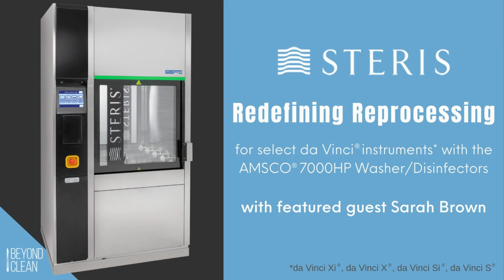something that changed in the U.S. market. Back in 2018, the FDA provided guidance around reprocessing for robotic surgical instruments with the idea that they were trying to help standardize applications there. And what happened was the FDA provided guidance that required washer disinfector manufacturers to obtain a 510(k) clearance, specifically indicating them for use with the particular instruments. And in this case, what we're all talking about are the da Vinci EndoWrist instruments from Intuitive Surgical. And that's what changed. The FDA's guidance changed to require that 510(k).